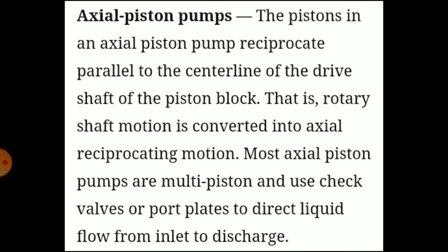So the pistons in axial piston pump reciprocate parallel to the center line of the drive shaft of the piston block. That is, rotary shaft motion is converted into axial reciprocating motion. Most axial piston pumps are multi-piston and use check valves or port plates to direct liquid flow from inlet to discharge.